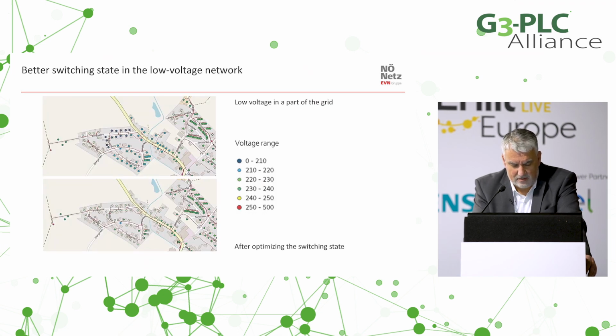A second example: on the top you see it's also a little bit dark blue, meaning we have a problem with the voltage, and we have to optimize the switch state of the low voltage grid. After we have done this, everything is good. We have a good voltage, and we see in a very short time what we have to do, and where the voltage is good or not good.